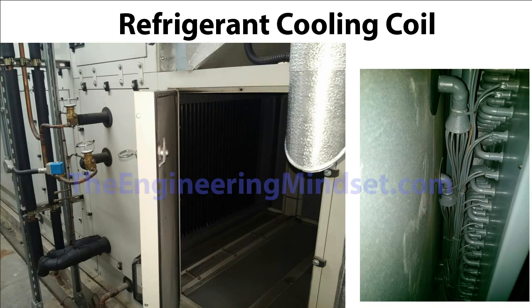You can always tell if the cooling coil is refrigerant-based because it has expansion valves, usually directly outside the coil. And from the inside of this coil you can see it splitting away and feeding off into multiple smaller tubes and into the cooling coil. This type of cooling coil is controlled by a capillary tube just inside underneath this lagging, which rides up and comes through onto the diaphragm of the expansion valve — that controls the refrigerant through the metering device.